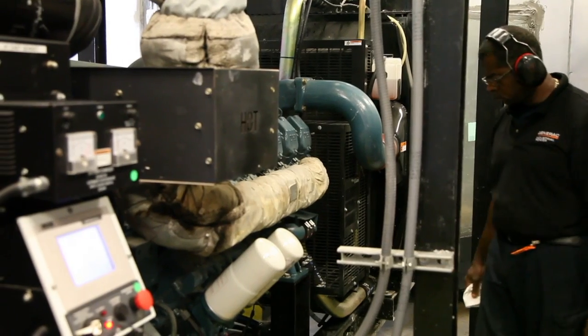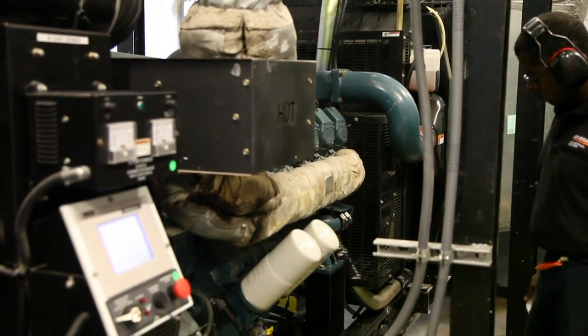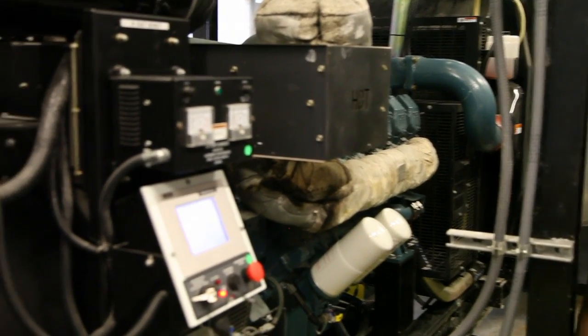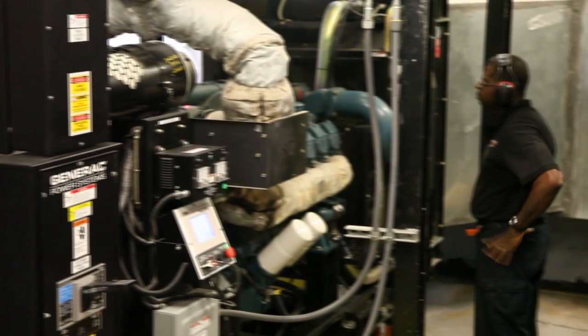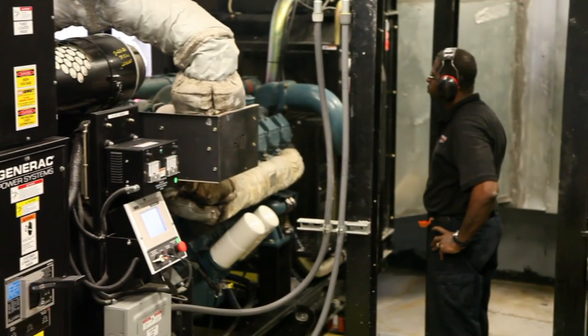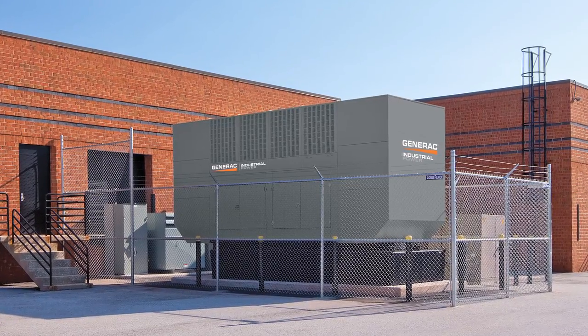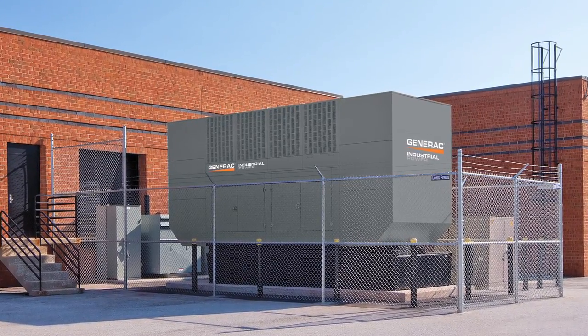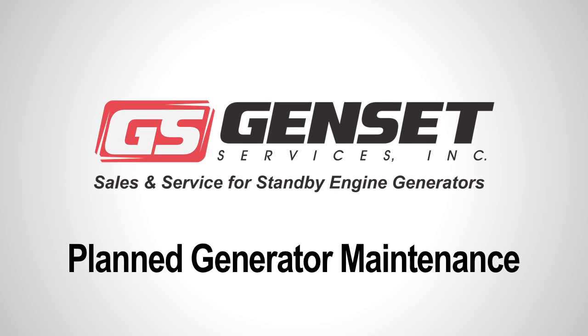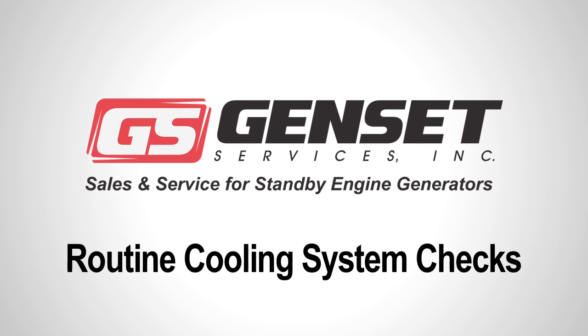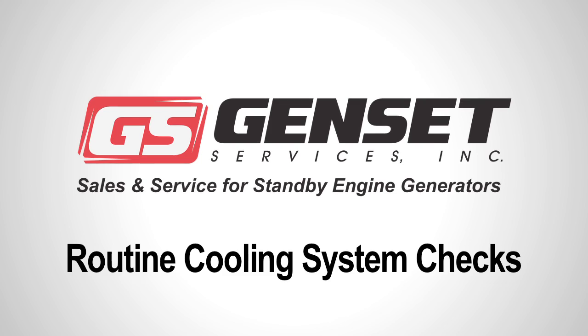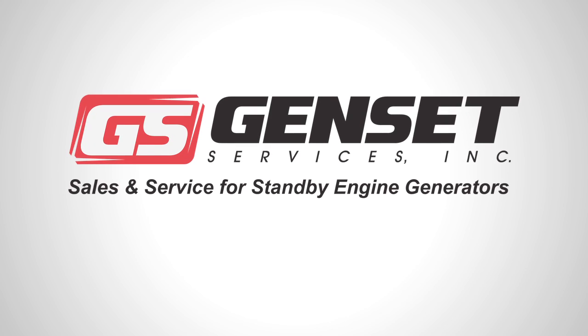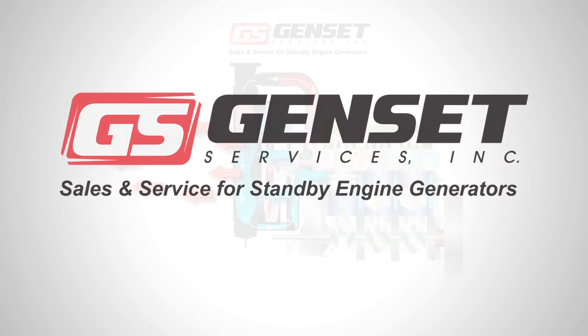Insufficient attention paid to its engine cooling system is frequently the reason a generator system underperforms or totally fails. Coolant levels falling due to leakage or faulty components will result in an engine running too hot, leading to temperature shutdown or even total engine failure. At Genset Services, part of their planned generator maintenance program routinely checks the entire cooling system, paying close attention to all the critical components relating to cooling.